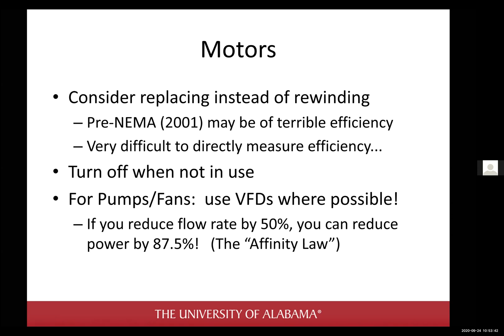And the last thing is, if you can use a variable frequency drive, please use it whenever possible. A VFD, or variable frequency drive, controls the frequency of the electricity going into the motor, allowing it to slow down or speed up depending on how fast you want the motor to go. Here's a really neat thing. If you can reduce the flow rate or the speed of a pump or a fan by 50%, there's this thing called the affinity law, see third year mechanical engineering, but anyway, you can reduce the power consumed by 87.5%. So there's a cubic relationship in there, which is pretty powerful.